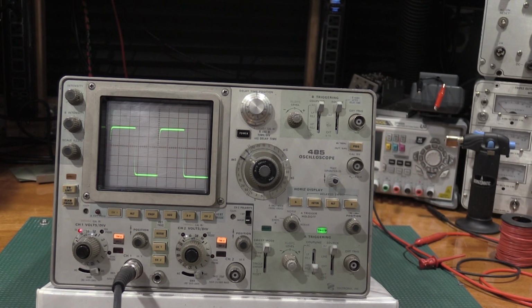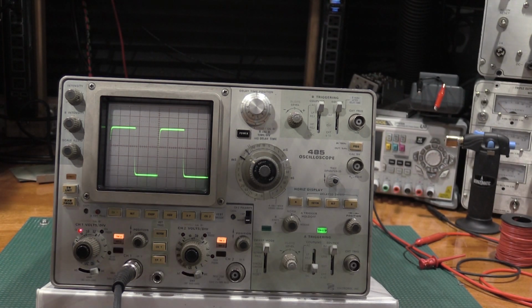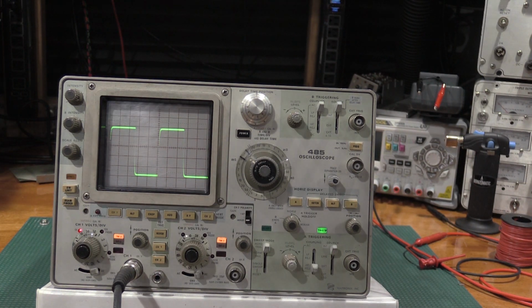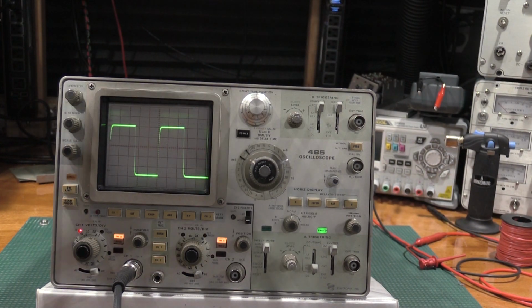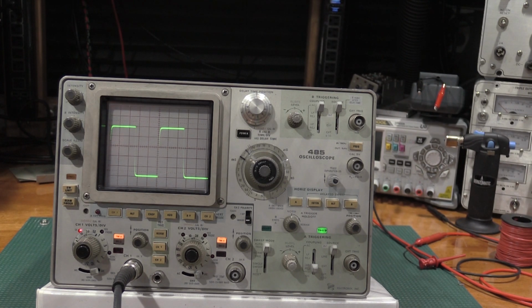Let's actually check this other range, this 10 millivolt range. If it's 4.5% low, 4.1% low, that's a good sign if all of them are that way, that it just needs an alignment. It's a little light at 4.1, probably 4.2, so probably going to be good with an alignment at this point.